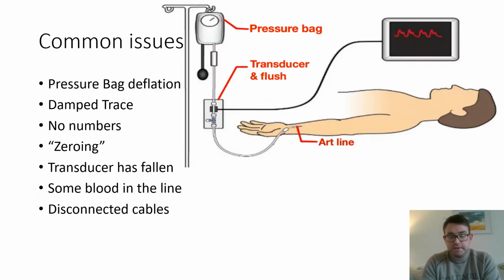Common but not serious issues that can occur with arterial lines. The pressure bag itself can become deflated. Usually there's a little indicator on the specialized pressure bag that tells you the appropriate pressure to create around that bag, so that there is a constant pressure that the transducer can act upon. It's also very important that the fluid within the pressurized system is normal saline or 0.9% saline, nothing else.